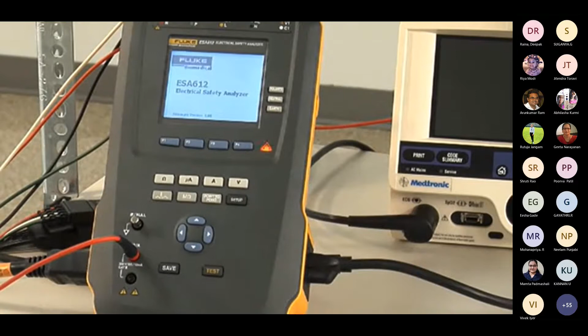If you need to test more than 5 applied parts, the 1210 adapter box is provided as an optional accessory. Here we're performing leakage tests using the analyzer connected to an ECG monitor via the 1210 adapter box. This allows for the RA, LL, LA, and RL leads to be isolated from each other and from the remaining chest leads, which are shorted together.